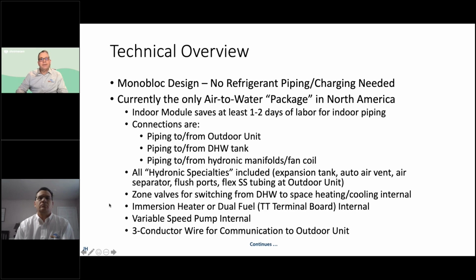What that means is the indoor module is a key part of that. There are other air to water units out there, but they're just the outdoor portion of it. So all of the indoor piping components and so forth has to be done in the field. We think it's about 1 to 2 days of labor savings, because what you end up with are just piping connections. So you're piping to the indoor unit from the outdoor, you have your piping to and from the indirect water heater and out to your hydronic zones. That's really it. You connect your manifolds and so forth.